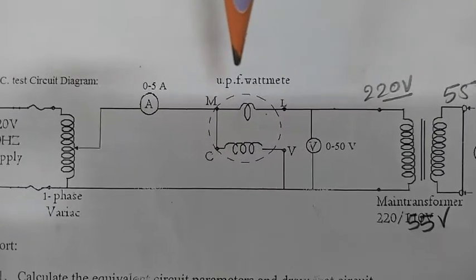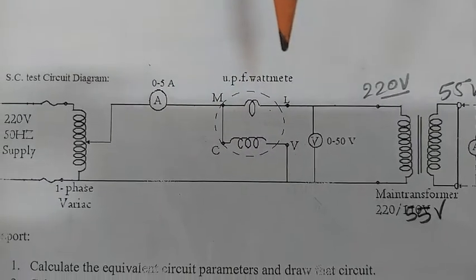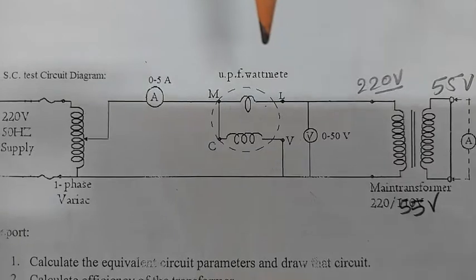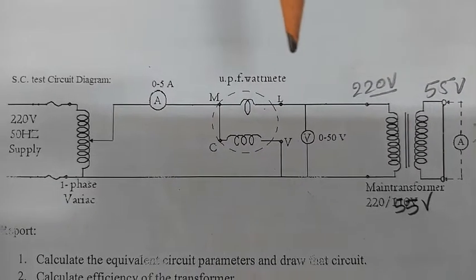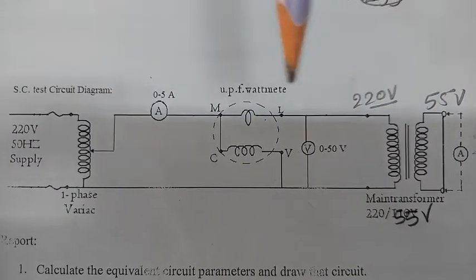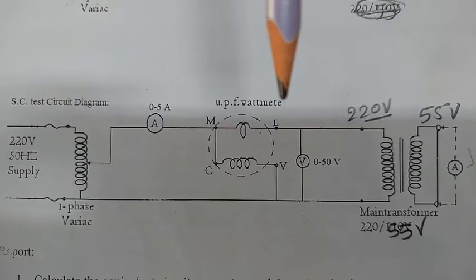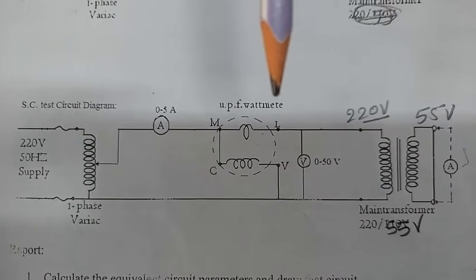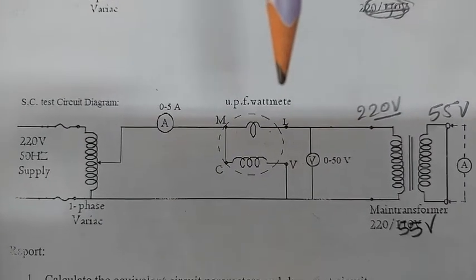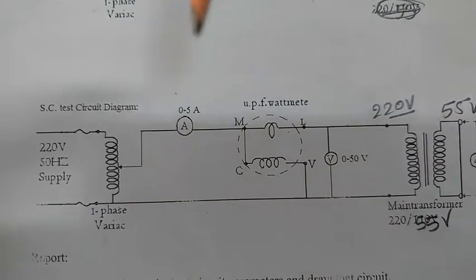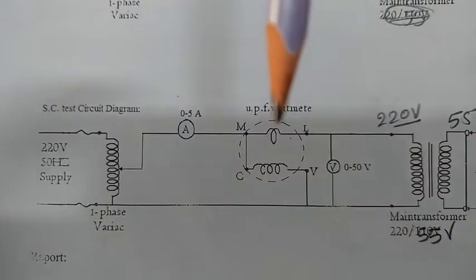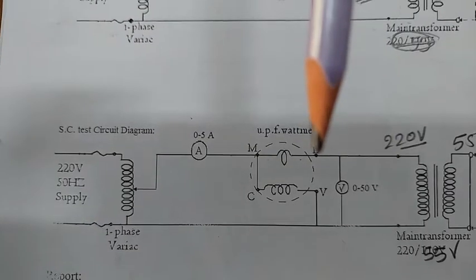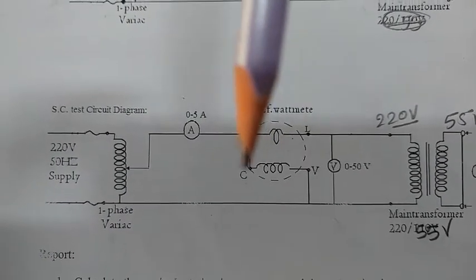Here you can see the M, L, C, V points, which are very well known to all after discussing them several times during the theoretical classes. So M and L will be the current coil, and C and V will be the pressure coil or voltage coil. M stands for main, L stands for line, C for common, and V for voltage.